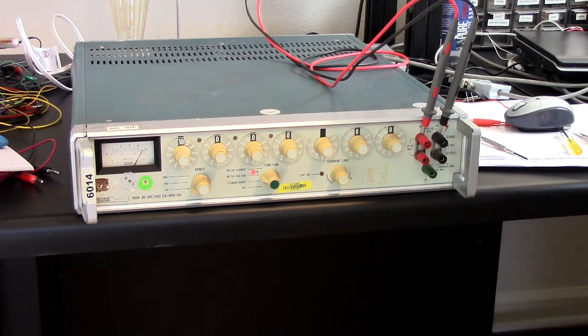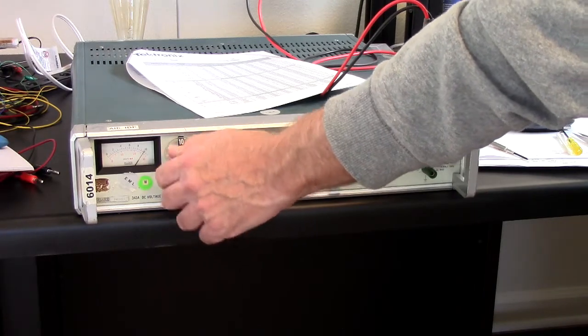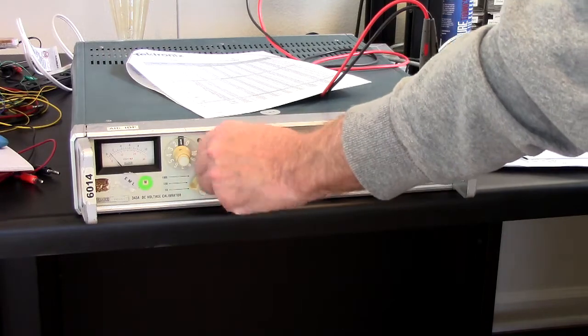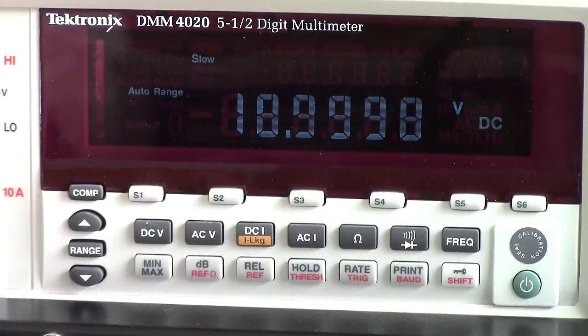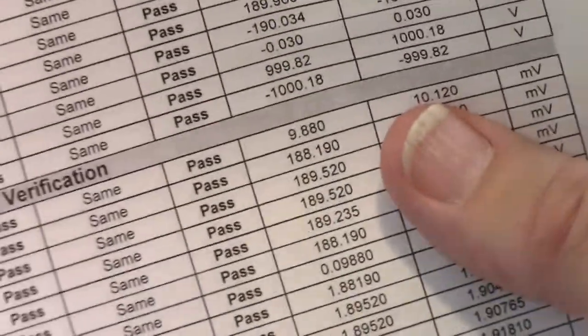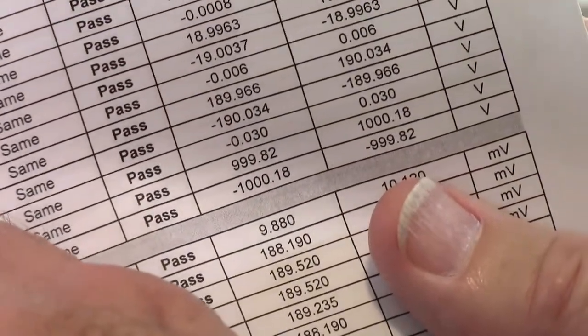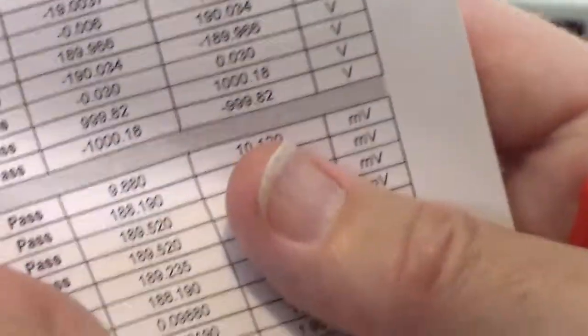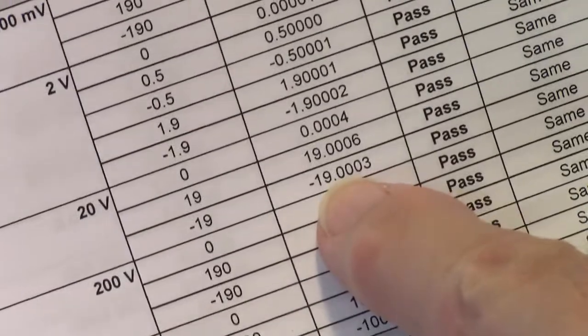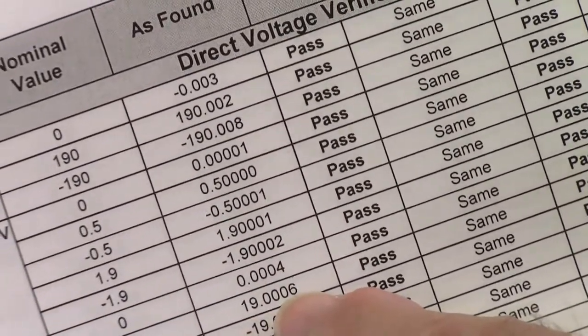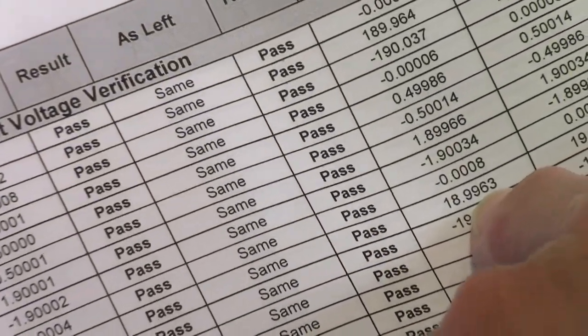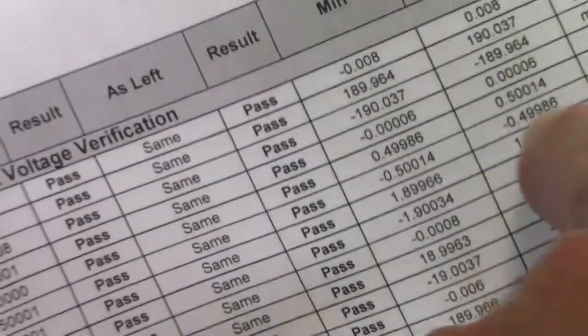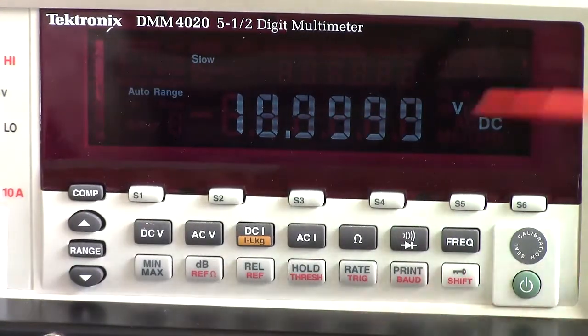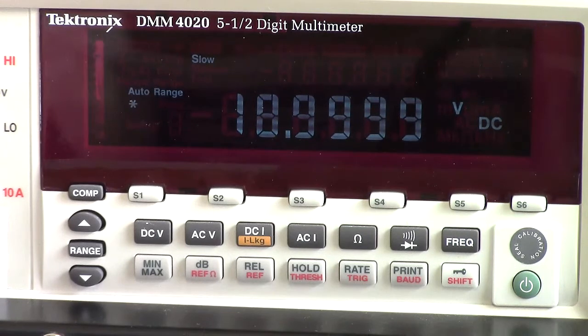19 volts. At 19 volts, I'd have to go to the 20 volt scale and go to 19. Okay, that's 19. And the readout on that was somewhere here. 19.0006. Where is it? Oh, way over here. Okay, 19 volts, 19.0006. Anything between 18.9963 and 19.0037 is in spec for this meter. Well, I've got 18.999. Pretty darn close, and that's just out of the box. So this is looking good.